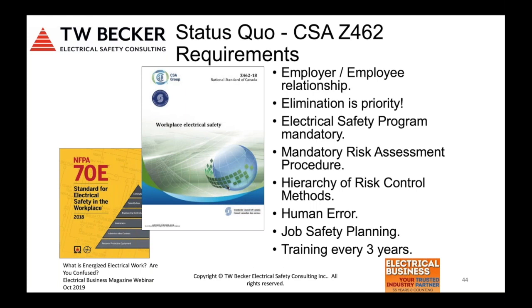So employer-employee relationship, elimination is the priority, but energized electrical work is allowed. It is allowed, but you have to follow the policy and practice requirements associated with it. An electrical safety program is mandatory and appears right at the front of these standards. And I still believe industry doesn't have electrical safety programs developed, or they're not compliant. There's a mandatory risk assessment procedure in the latest editions. Hierarchy of risk control methods is now mandatory. It was moved from a note into the chapter, into the article or the clause. Human error was identified and propped up in the latest editions. Job safety planning is now a mandatory requirement that shall be documented by the qualified person, and training is still every 3 years.